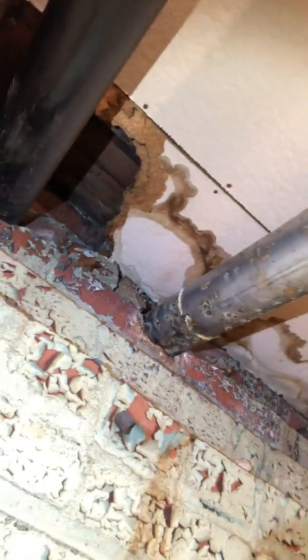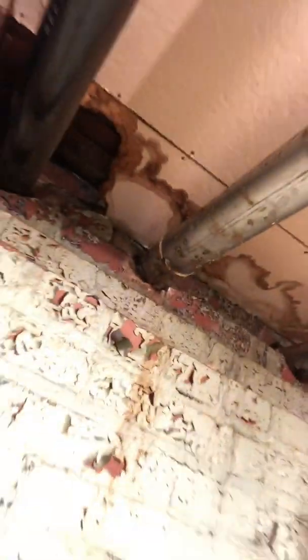I have multiple other flue pipes. See all those little black dots? Little specks? Those are pinholes. Flue gas is coming out of there. Not good.